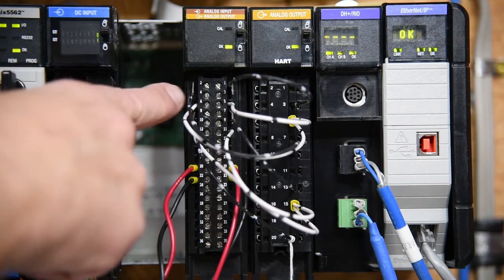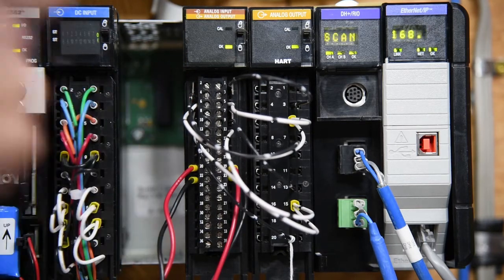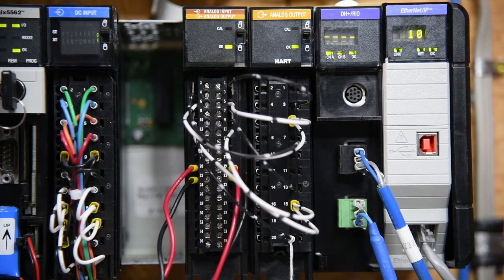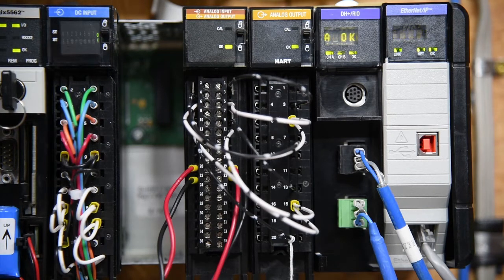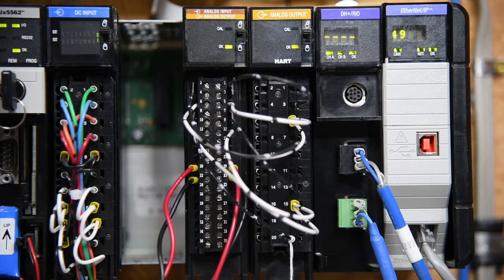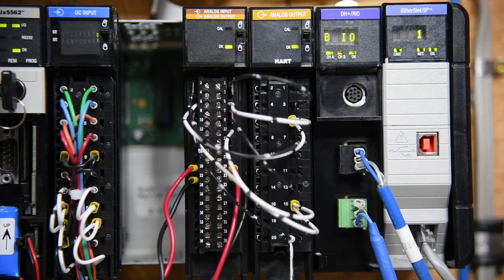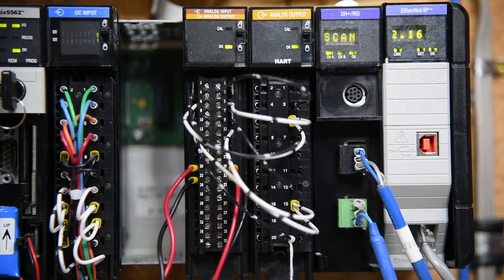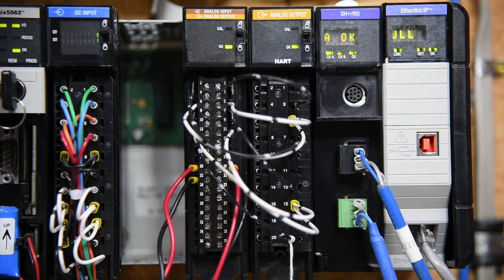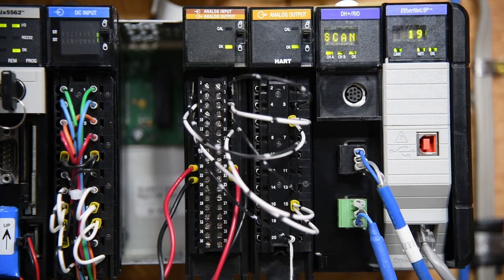If you don't have that jumper there, you are going to get all kinds of really strange readings in your program on your display screen. So that is the main difference between wiring the current or milliamp inputs and the voltage inputs.